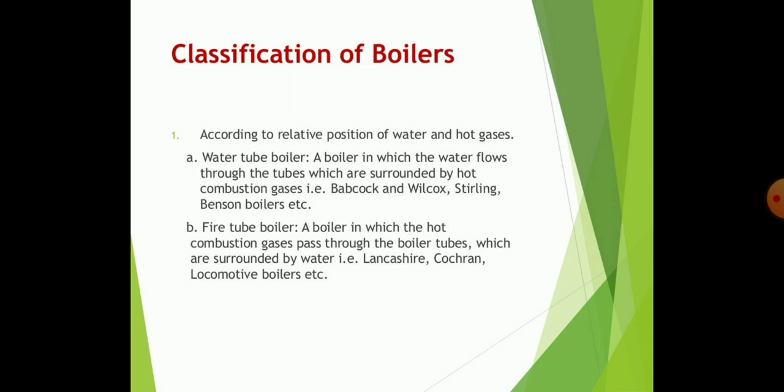For achieving this purpose, we can classify these boilers into water tube boilers and fire tube boilers. Water tube boilers are those in which water flows through tubes that are surrounded by hot combustion gases, such as the Babcock and Wilcox boiler. Fire tube boilers are those in which hot combustion gases pass through boiler tubes that are surrounded by water, such as the Lancashire boiler and Cochran boiler.